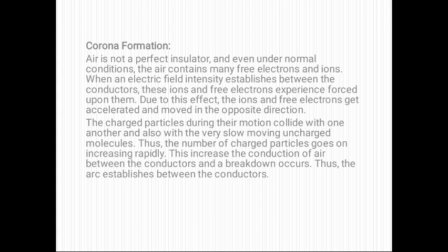Now, formation of corona, how it is created. We know that air is not a perfect insulator, and under normal conditions air contains many free electrons and ions. When an electric field intensity is established between the conductors, these ions and free electrons experience force. Due to this effect, the ions and free electrons get accelerated and move in opposite directions. It means when a charge comes in the electric field of another charge, it experiences force, due to which this charge moves from its position.